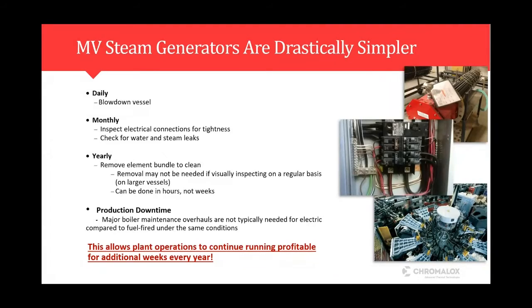With the electric side, these systems are much more simple. And from a maintenance perspective, it's pretty straightforward with what we recommend. Obviously, you have your daily blowdown sequence, which again, is not specific to electric. The fuel-fired systems should also have some type of regular blowdown maintenance. But from a monthly perspective, we recommend just inspecting the terminals for tightness, because one of the issues is the flexing from the heat and cooling that these terminals see, and they can come loose. So that's one thing we recommend: on a monthly basis, go through, retighten and check those terminals.